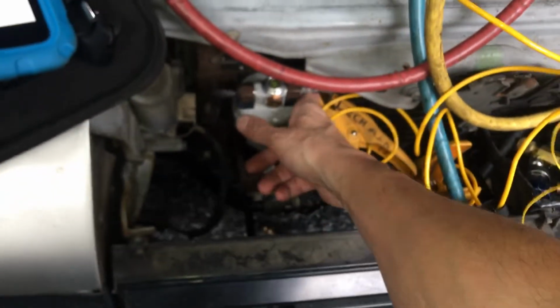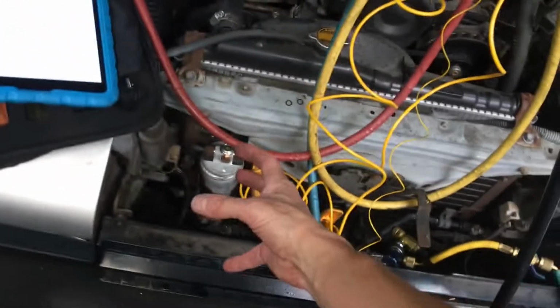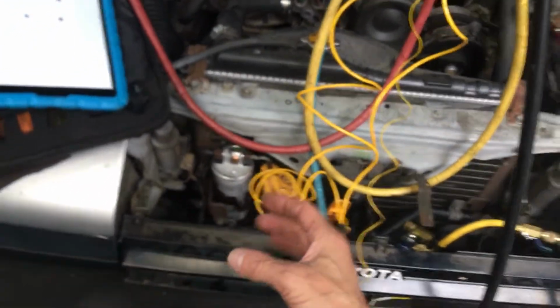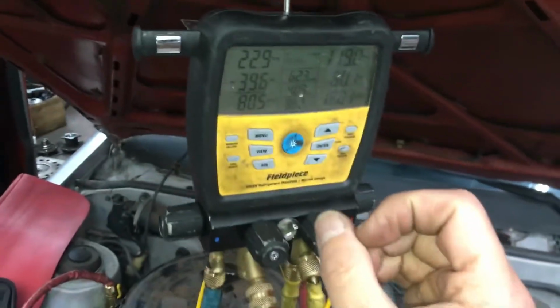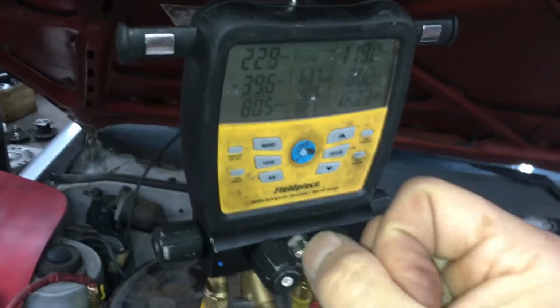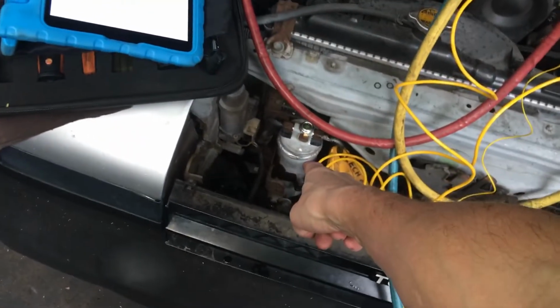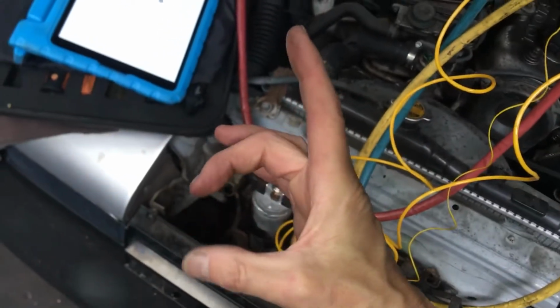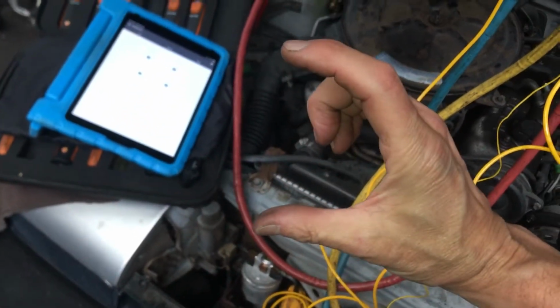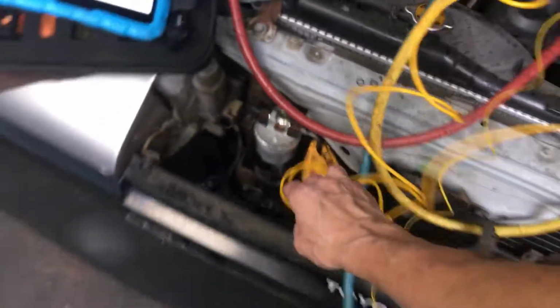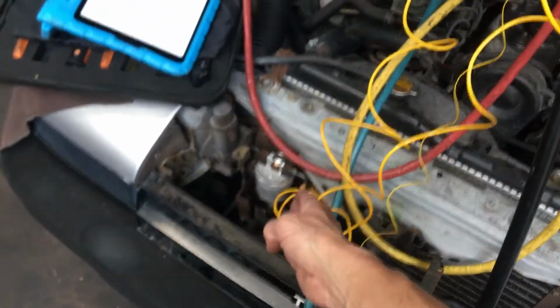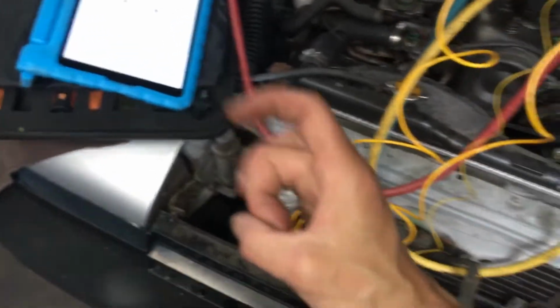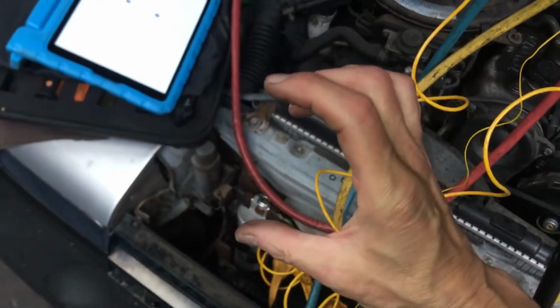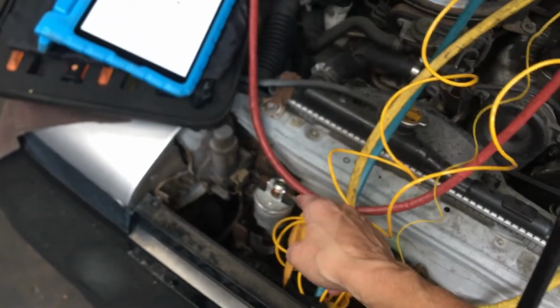Now, one thing that is wrong that I would change, this receiver dryer is so big. This receiver dryer was meant for a large quantity of liquid refrigerant. Because we're using a propane butane mixture or either or, we have a very little quantity of refrigerant. So you do not need a dryer this big and round. The more round you go, the more refrigerant you need to fill it up, so you get liquid coming out here. So the problem is this is too big of a dryer, especially wide-wise. You just need a little narrow dryer, a little small one with a pickup tube in the bottom, so you could get pure liquid refrigerant without vapor.